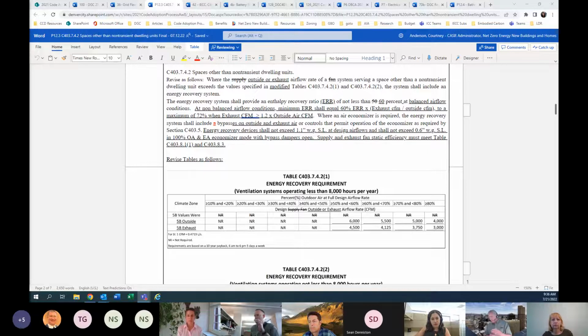Can I also comment? Well, yeah, if I may, I will also comment on the industrial or institutional and laboratory stuff. I may have mentioned I get millions of square feet of hospital and all that stuff. Again, we are subject to a lot of different authorities having jurisdiction. I think this is a good way to allow for us to say that we can't use a leaky heat recovery system in these areas, even if you would, because it's just environmental air. But ASHRAE 170 says that air coming from certain types of areas of the hospital can't have leaky heat exchangers.